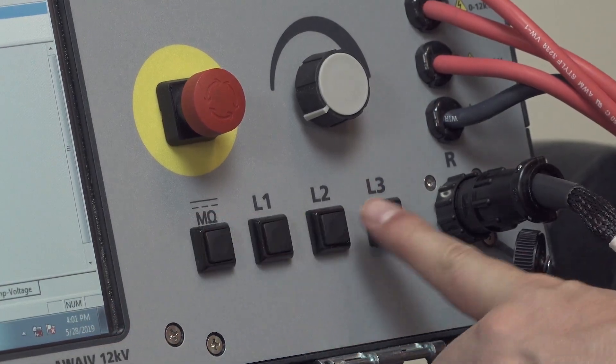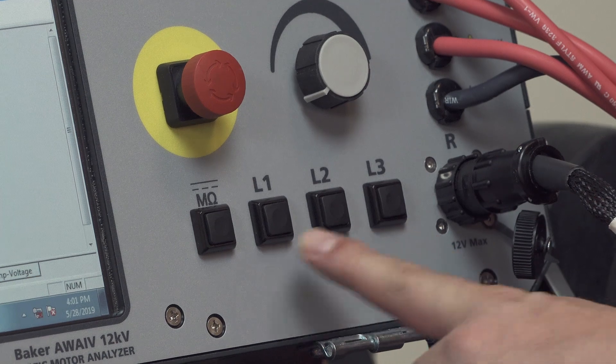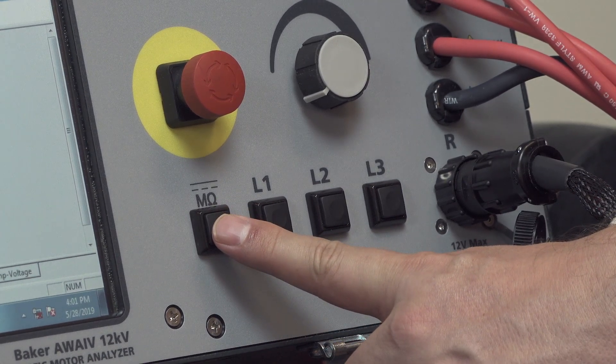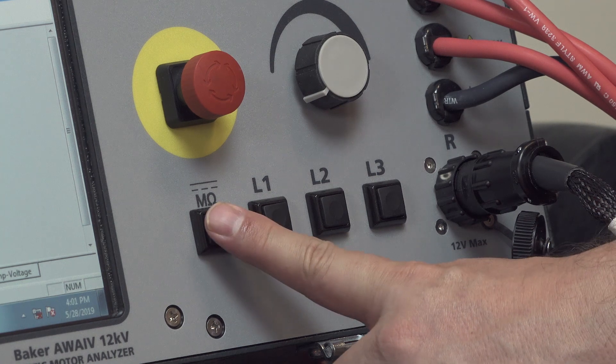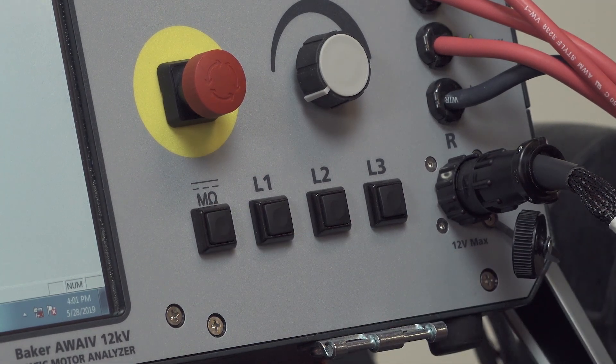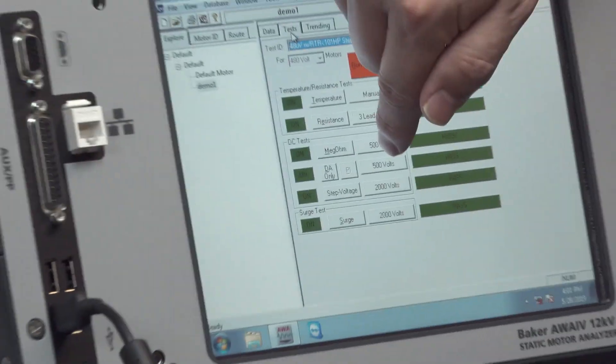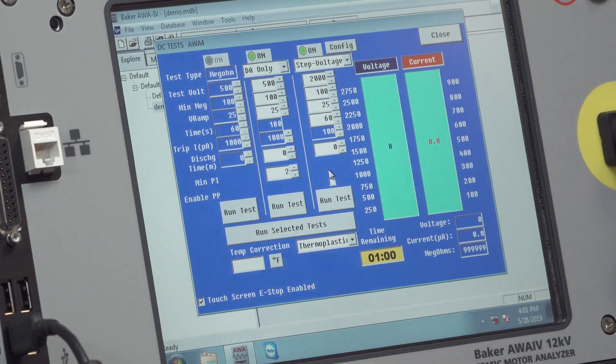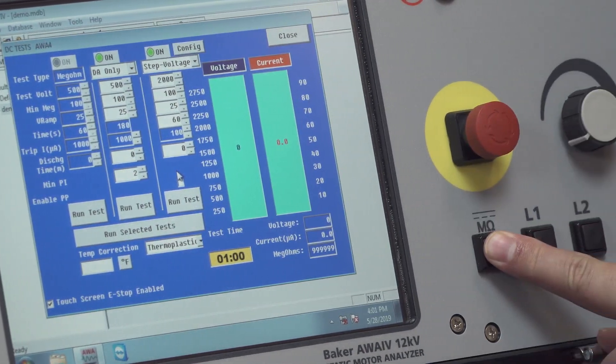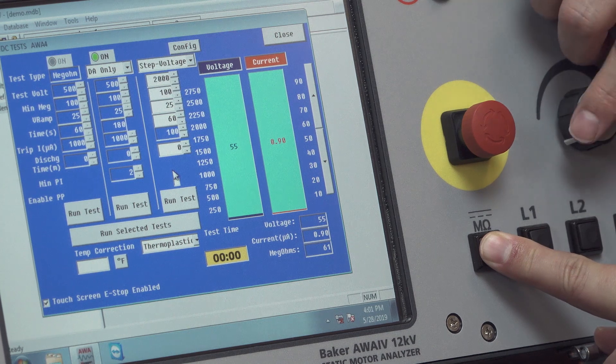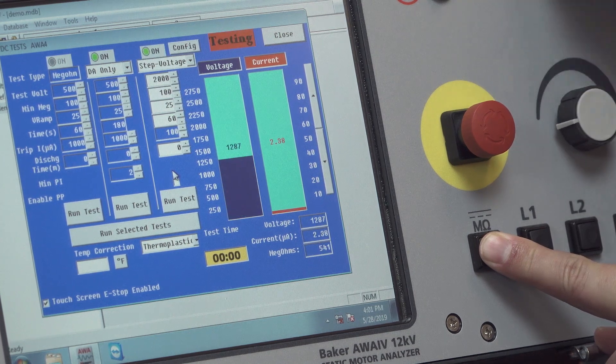Then we have the push to test buttons along the bottom here. One's labeled megaohm DC. This is for doing manual DC testing. You'd have to be on the proper test screen for DC testing. And then by depressing the megaohm DC button, you can perform a manual high pot test using the potentiometer to control voltage.